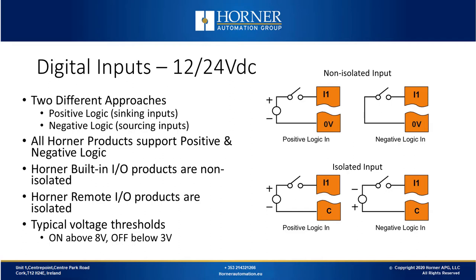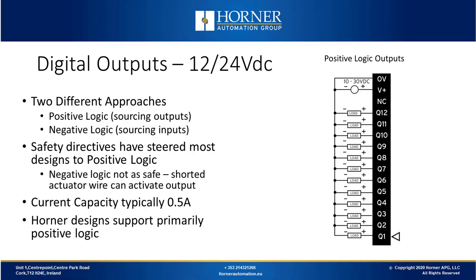On the digital output side, there are two different approaches. You've got positive logic, where you're providing the positive voltage to the actuator and then the actuator is connected externally to common. With negative logic, it's the opposite — the output module is providing the negative lead and the positive lead is coming externally. Our designs at Horner primarily support positive logic, and the current capacity is almost always about half an amp.